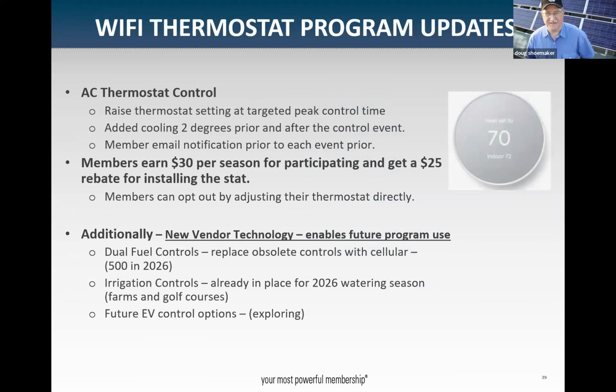This is the thermostat control I mentioned. We've been doing this for a while and just got a new system for it. Rather than cycling the air conditioner on and off every 15 minutes, we know when the control period is coming. So if we want the air conditioner off starting at 5 o'clock, we'll pre-cool 2 degrees under the typical set point for 90 minutes beforehand, then raise the set point 4 degrees during the control period, which typically runs 2 to 4 hours. If the house gets warm enough to hit that 4-degree increase, the air conditioner can still turn on, and once the control period ends it goes back to the normal set point and cools the house back down. This has been very successful with a lot of people enrolled, and we're looking to expand it. It's been a good savings for us, and we pass the savings on to the members.